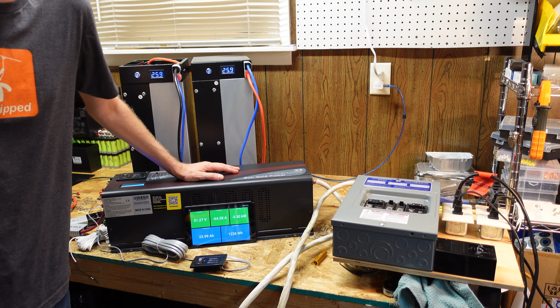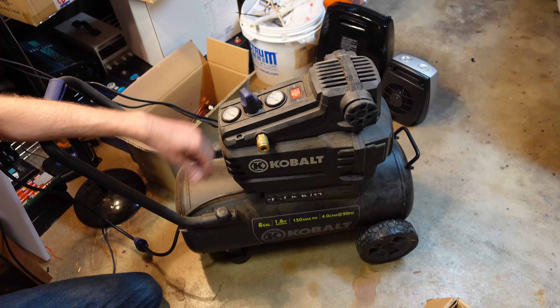While the discharge test is running with those space heaters, I want to try one more thing: starting a heavy inductive load. I have my Kobalt air compressor, 8 gallons, 1.8 horsepower. Not many inverters can start this, so let's see if this inverter with these batteries is able to do the trick. Here we go.